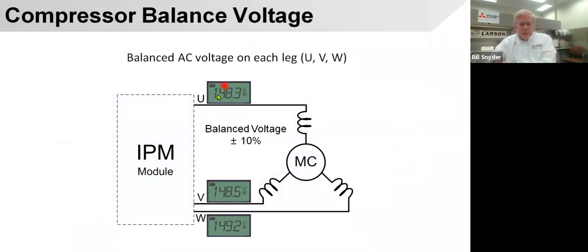I always say there's a difference here because we're varying the speed of the compressor, and when I'm checking out a compressor, if I'm not in test mode, I'm always listening to hear a pitch change. If you hear a pitch change, the compressor just slowed down or sped up. And if it's slowing down or speeding up, you're going to see these voltages change. So when you're doing these checks, you're going to check them fairly fast and listen to make sure that it's not changing voltage or changing the speed.